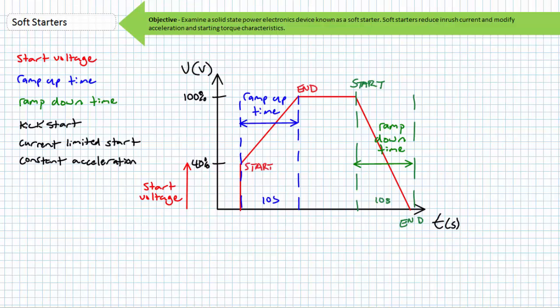This particular graph shows the soft starter upon being enabled starts at 40% of full voltage upon receipt of an input signal. If this is a 120 volt line to neutral or 208 volt line to line light industrial 3-phase AC system, this would mean the starting voltage is 48 volts line to neutral and 83.2 volts line to line. This graph illustrates the soft starter would take 10 seconds to ramp up the applied voltage from 48 volts line to neutral, 83.2 volts line to line, to the full 120 volt line to neutral, 208 volt line to line upon receipt of the input signal.